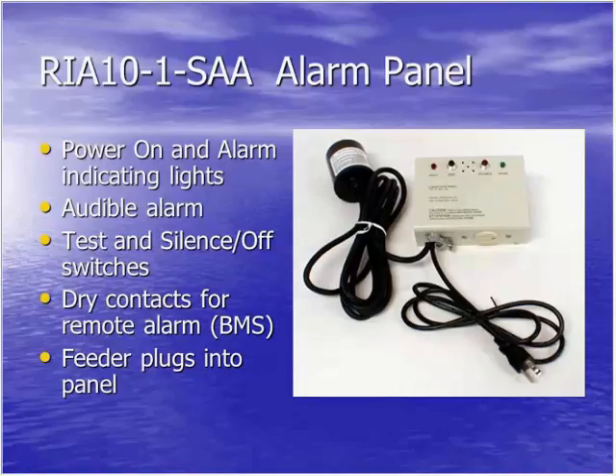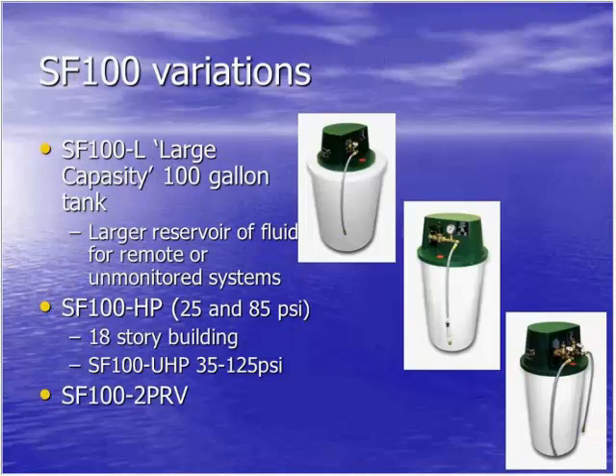We also build several different variations of this unit. An SF100L that has extra large storage, so a 100-gallon tank. This is typically used in very large systems or in remote locations. The SF100HP, which is a high pressure version for high pressure applications. And we have a 100-2 PRV, with which you can utilize one system feeder to feed two separate closed loops. So as long as the fluid that's being used in the system is compatible for each closed loop, let's say it's a chilled water system and a heating system, you can use one unit to feed both systems.